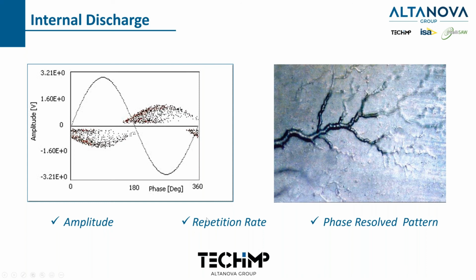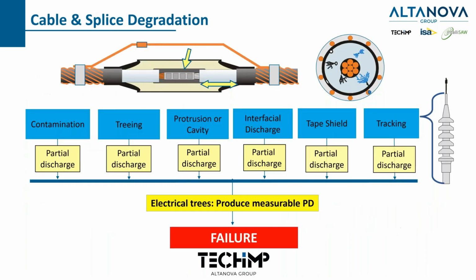And basically all this, what we do is give you a probability of failure, which allows you to replace or repair that asset before it fails. So what causes partial discharge? Well, all of this. I won't go through all of it, but we talked about contamination, treeing, protrusion, interfacial discharge. This is a little graphic of what water trees look like, and then once PD happens, what they look like. And of course, once this happens, it'll fall to the ground.